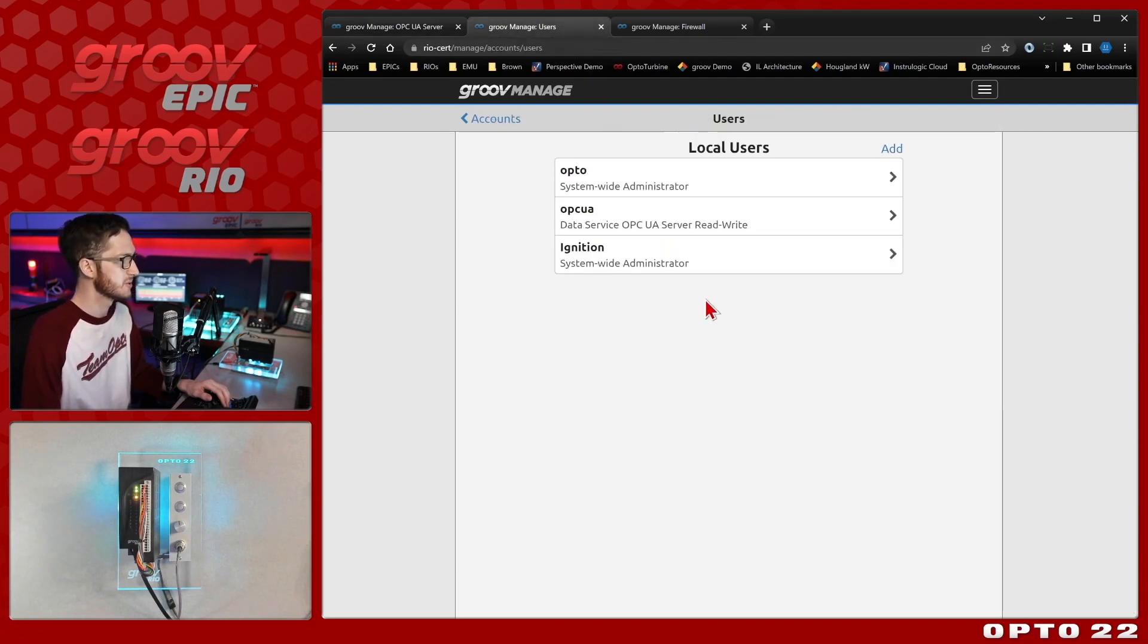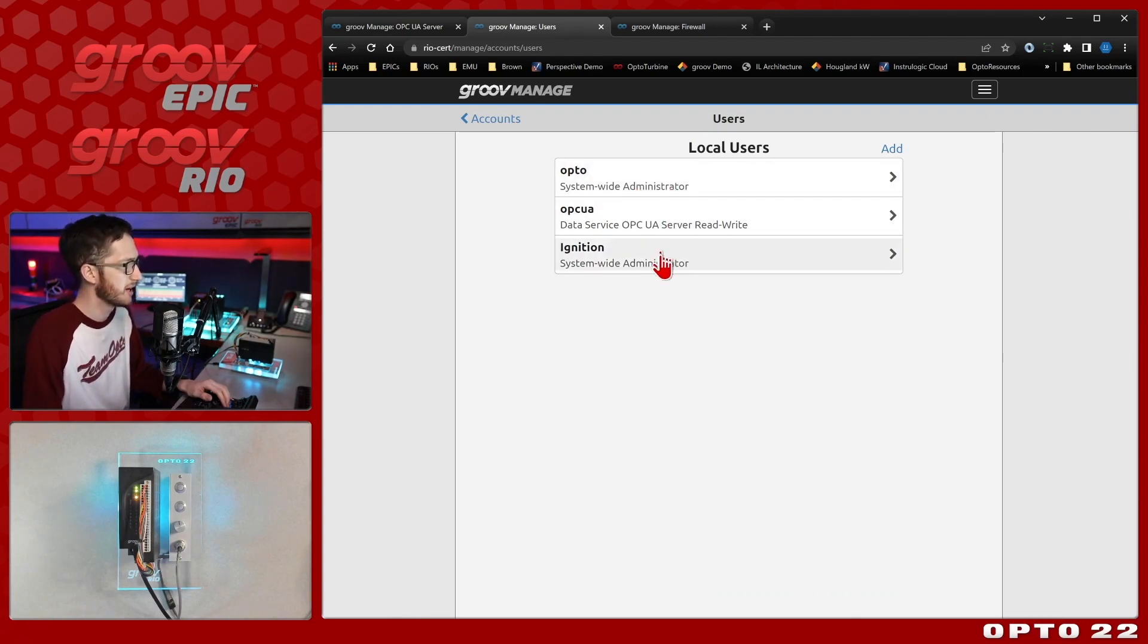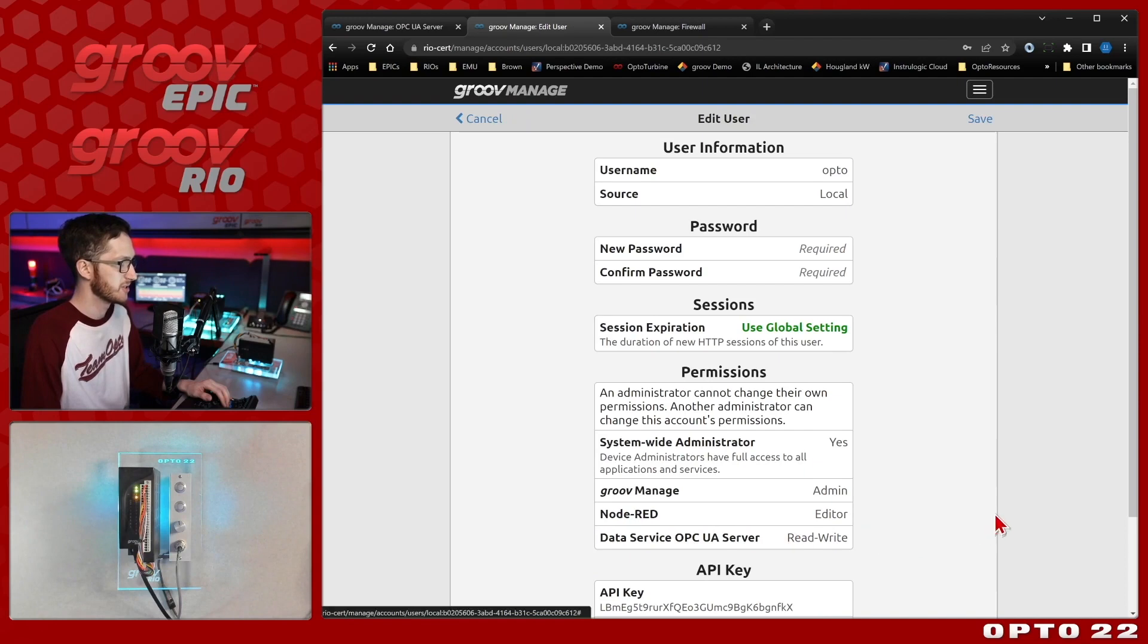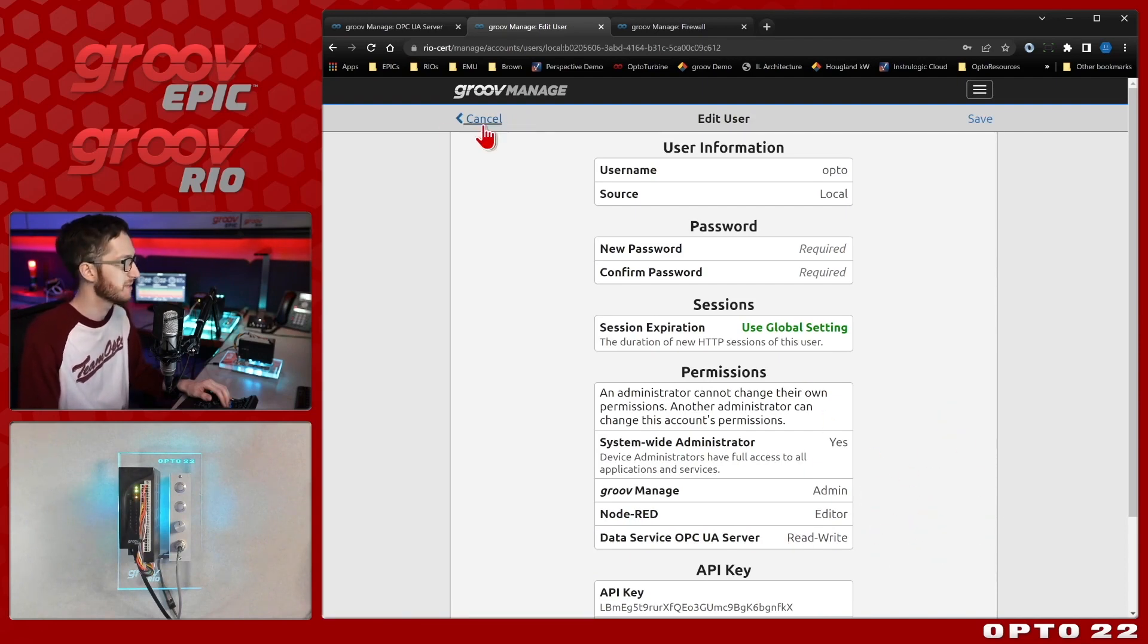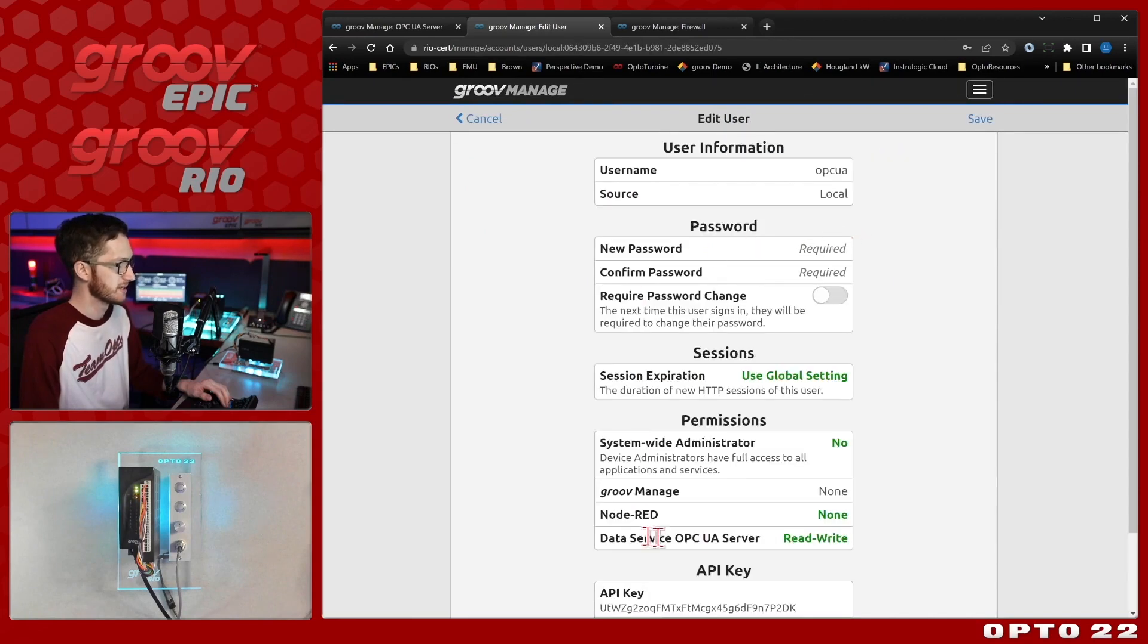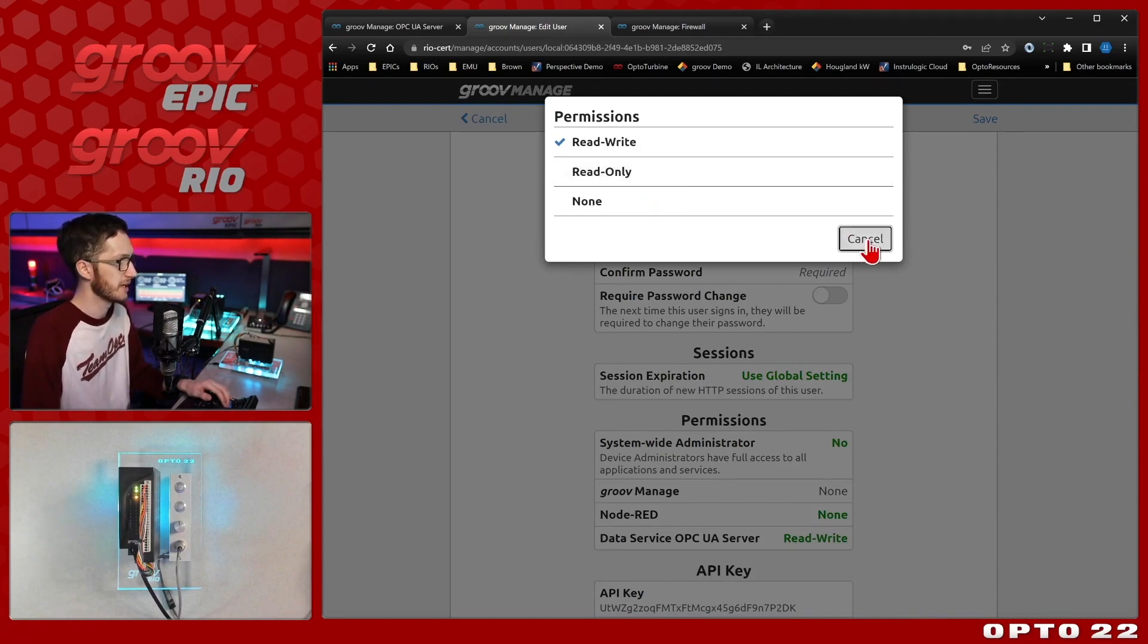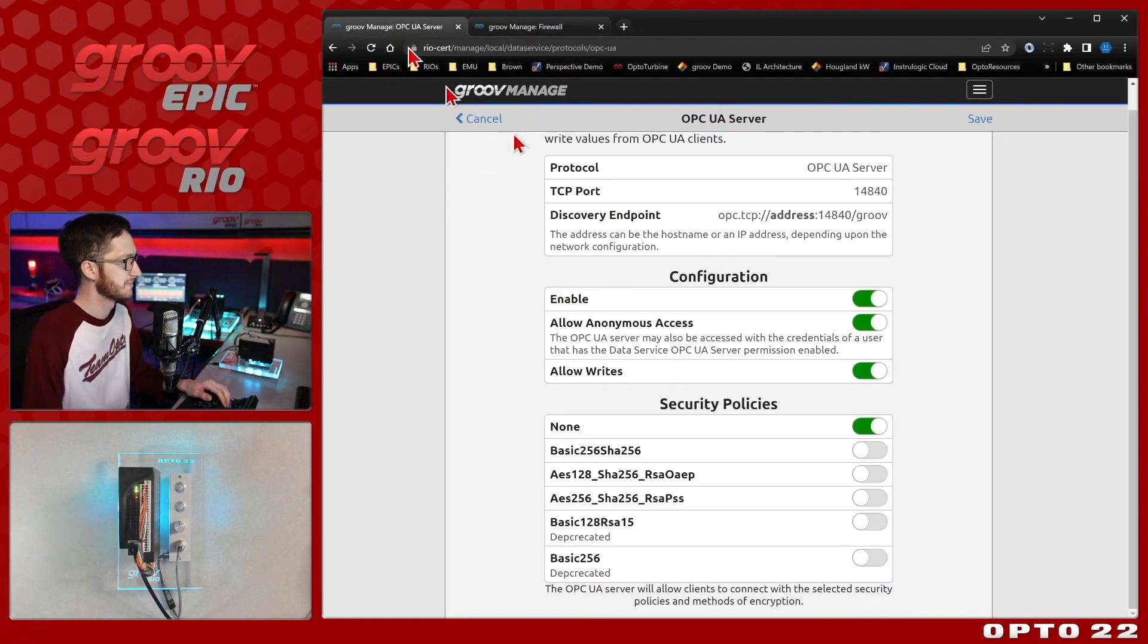And what does that exactly look like? Let's jump over to our users. This will work for LDAP users as well, but we're going to use the built-in groov Manage users. Here you can see I have system-wide administrators. If I select one of those, they do have read-write permission over the OPC UA server data service. And that's automatic. As long as you're an admin, you have access. So keep that in mind. But you can also create separate users like I have this OPC UA user here that just has read-write permission over the data service. I can also change this to be read-only if that's more appropriate for my particular application.